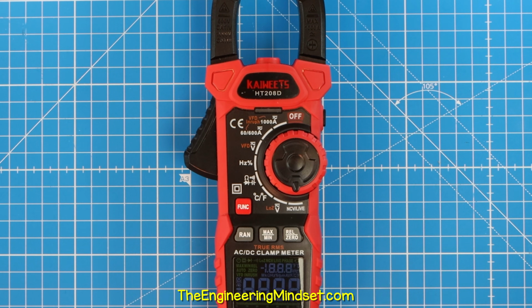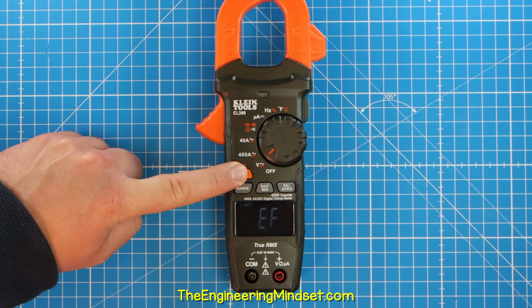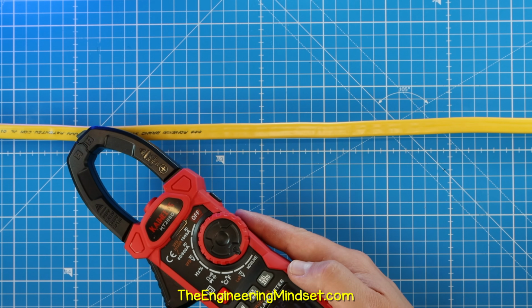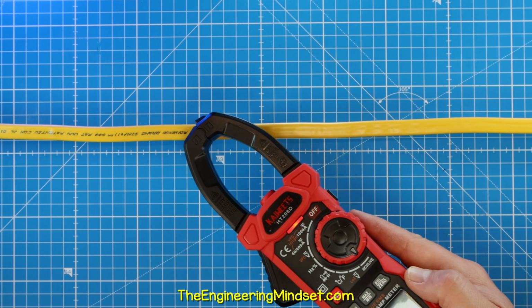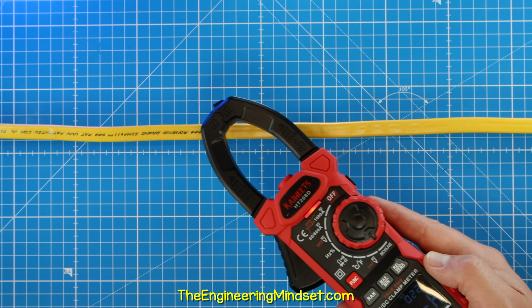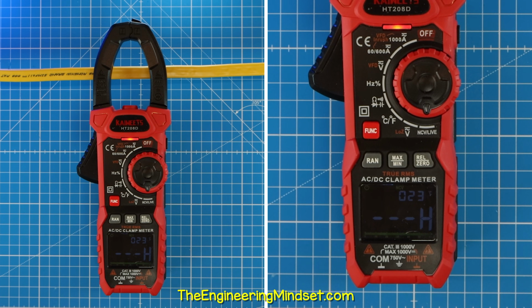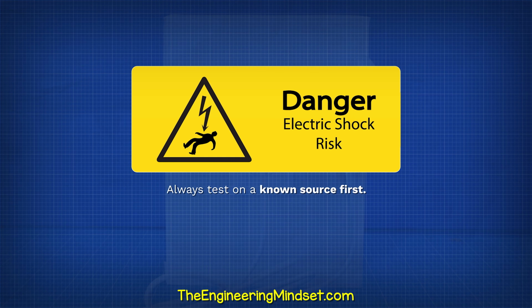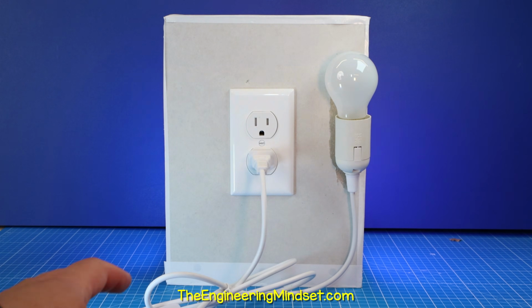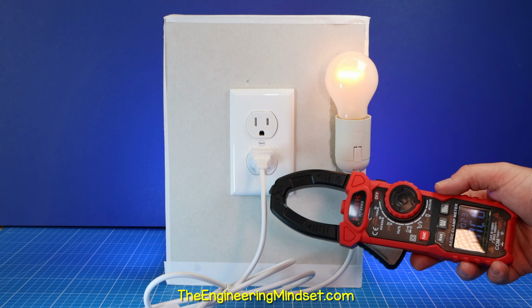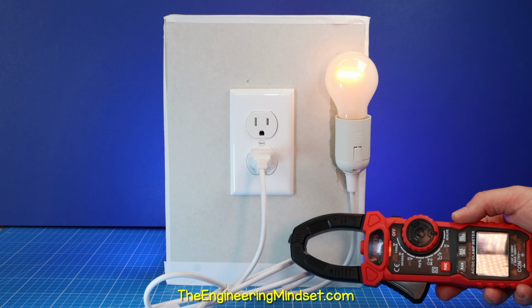We just select the NCV function or press and hold the button. We then move the sensor to the wire we are testing and it will alert us if a voltage is detected. It will not tell us the exact voltage. It will only tell us if it detects a voltage within its range. We must always test on a known source first. For example, this lamp, because we can see and verify that it is working.